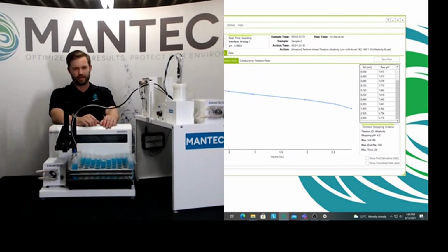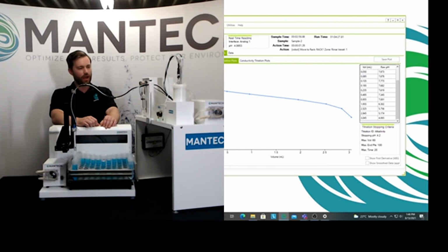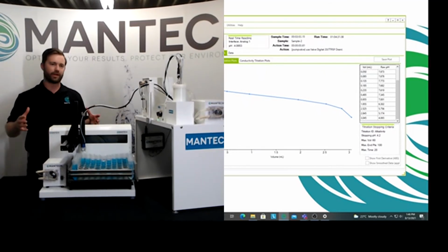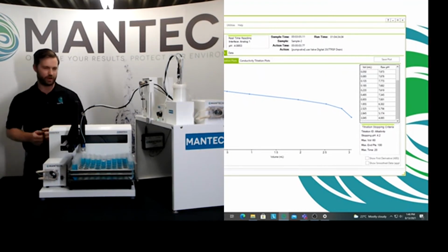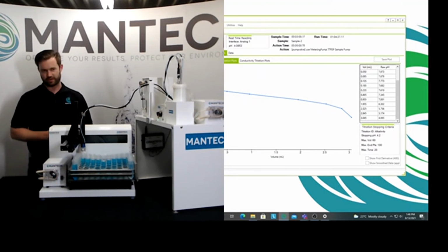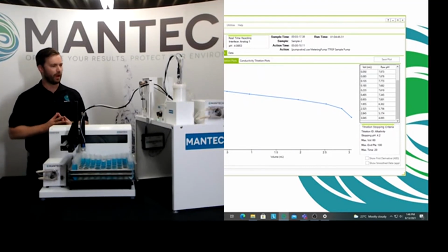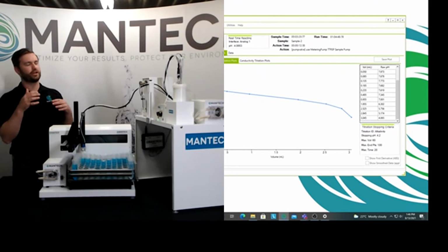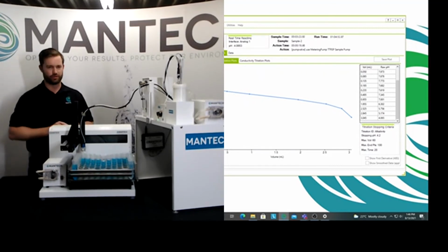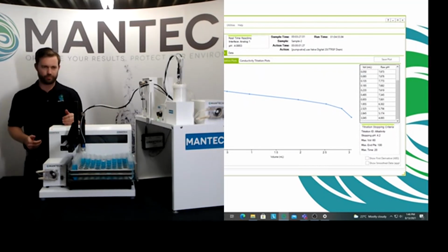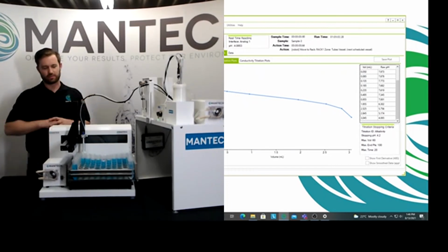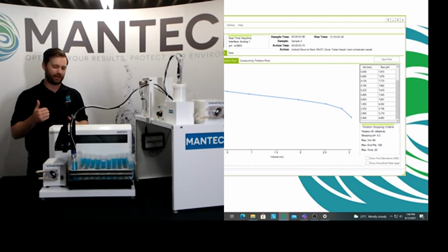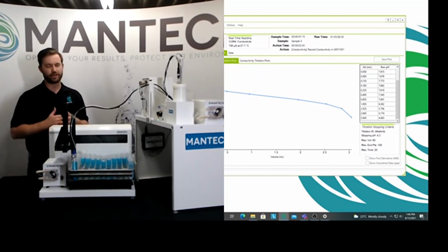That's it. So right there, you can see the titration curve live updating. And the burette right there is delivering that titrant in varying amounts. So it'll do small injections to start off, just making sure that it's not missing any low endpoints or anything like that. That's how we achieve our fairly low concentration limit. I think for alkalinity it is 0.3 or 0.2 ppm, something like that. And it essentially has a target change in pH that it's trying to achieve with every one of those injections. So it'll inject, see how much change in pH happens, and then it dynamically changes the next injection to make sure that curve ends up being nice and smooth and accurate, and you get a good result, highly precise every single time. It's the kind of titration you can really trust in.